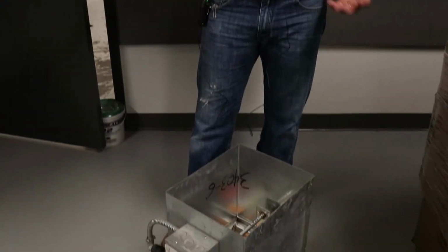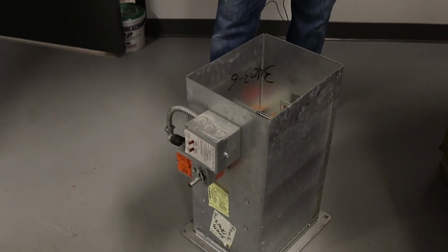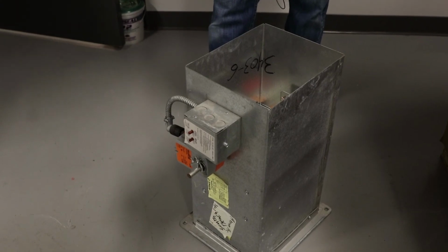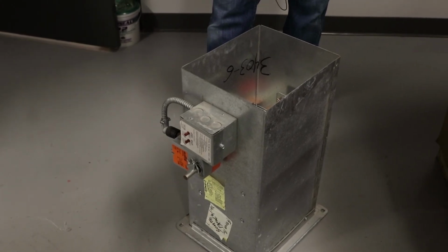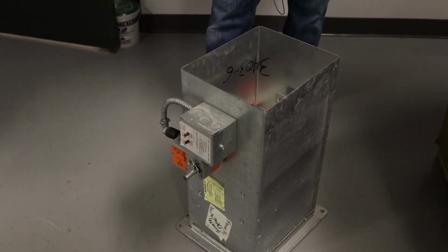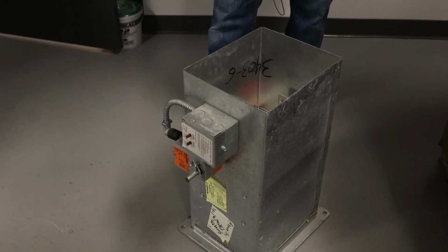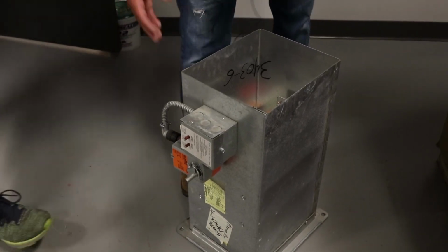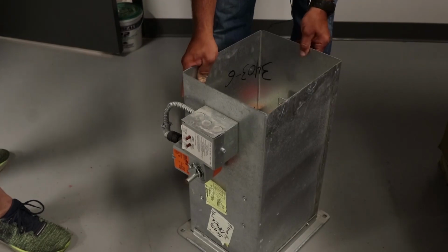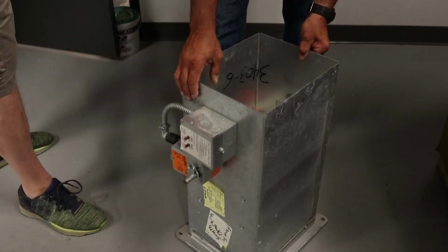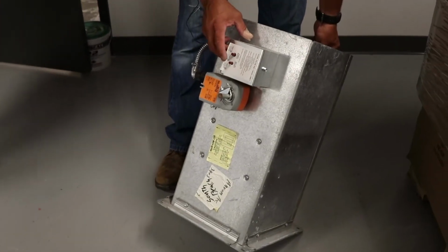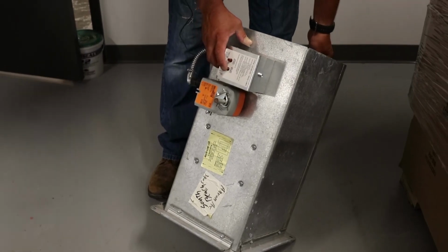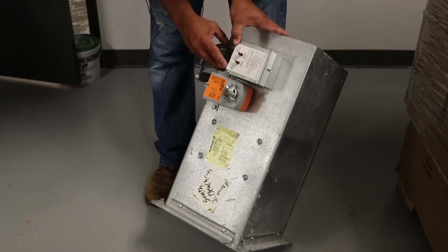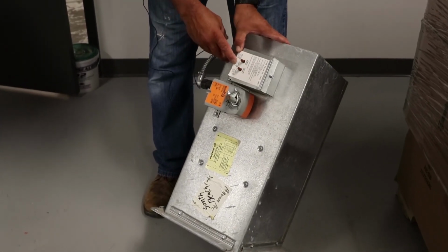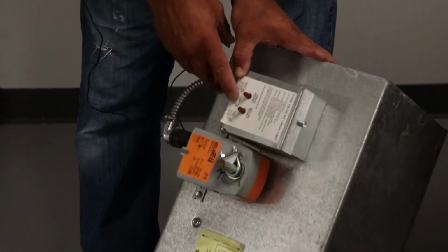Basically, all this does is sit. It's a sleeve in a wall. They're always powered on. In the activation of the fire alarm, whether it's through a test or through a fire smoke condition, the damper will lose power and it'll spring load closed. Inside this damper, there happens to be a primary reset and a high limit reset. You can see the scale where they trip, 212, 250, as is designated on the label.